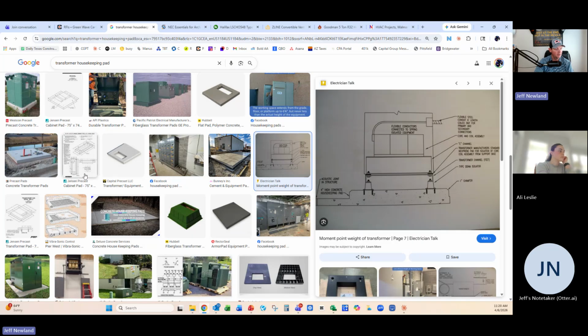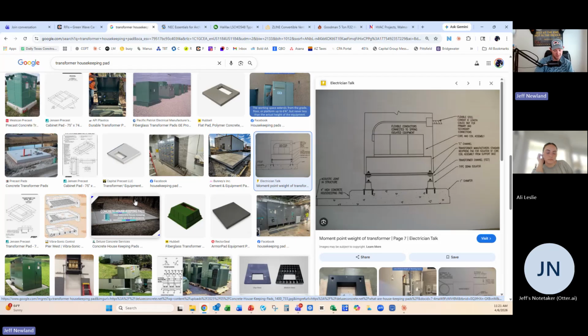100%, yes. Same thing with a condensing unit. On the Smitty's drawings that we started with, they didn't have a sidewalk or anything outside, and they didn't even show where to put the condensing unit on some of the drawings. Ideally, on a mini split system, you want the head to be on one side of the wall and the condenser on the other. The reason you want that is because it's the path of least resistance - you're going right out, right down, maybe through the wall, but you're in this wall.